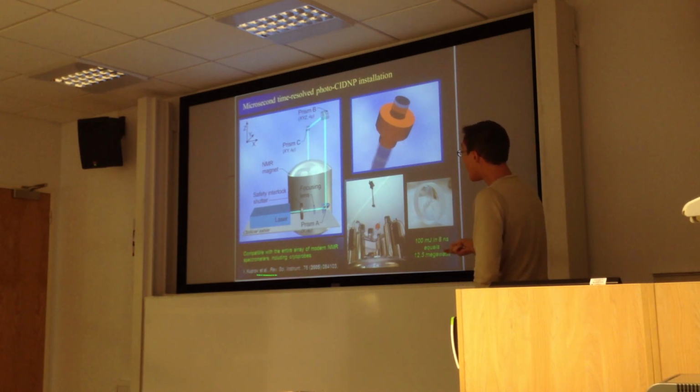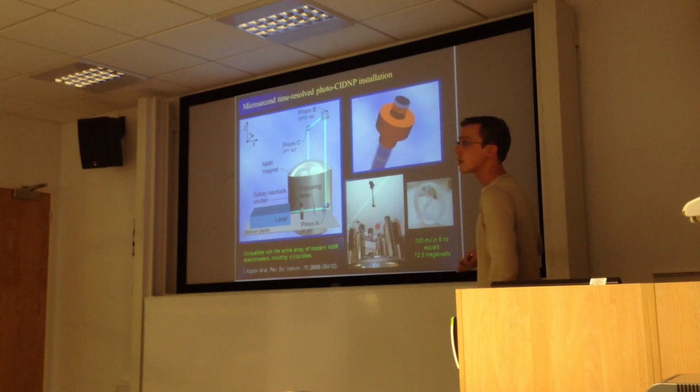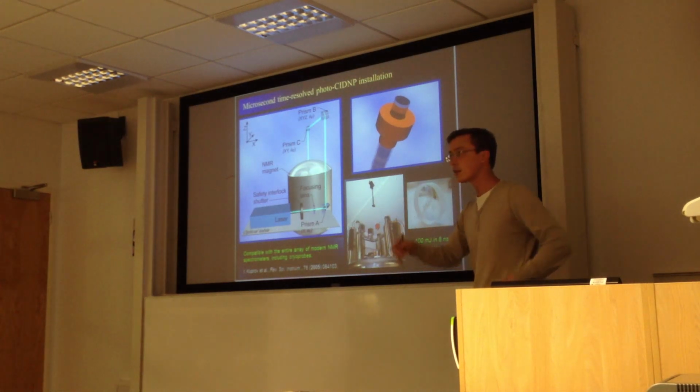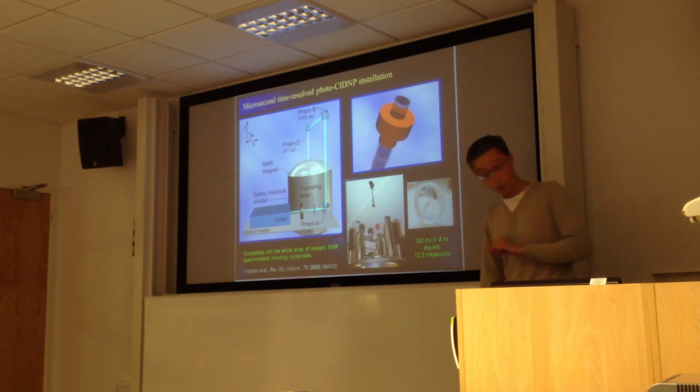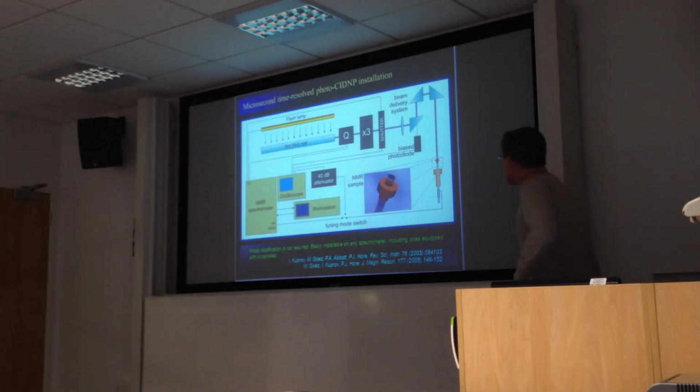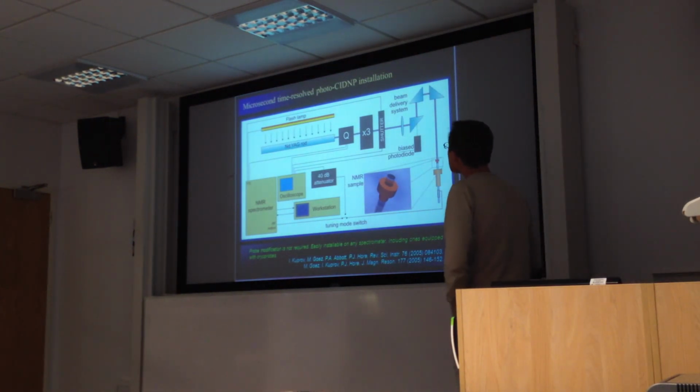But the good thing is this was working, and it was even compatible with cryo probes, because the illumination is from the top, and you don't need to drill anything or stick any sort of fiber into the place where liquid helium would have been. That's a schematic of it that went into Review of Scientific Instruments.